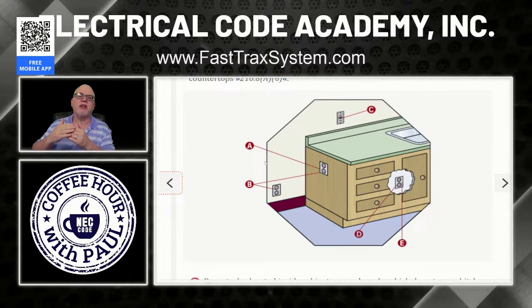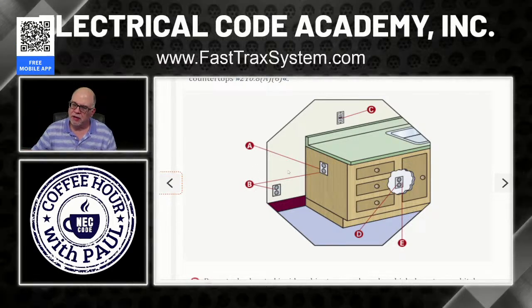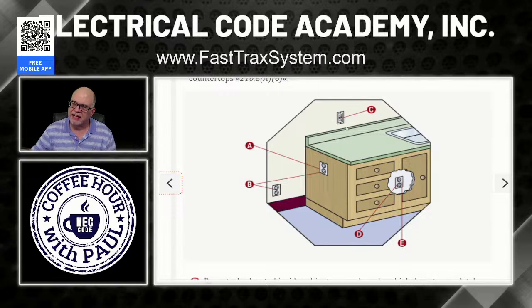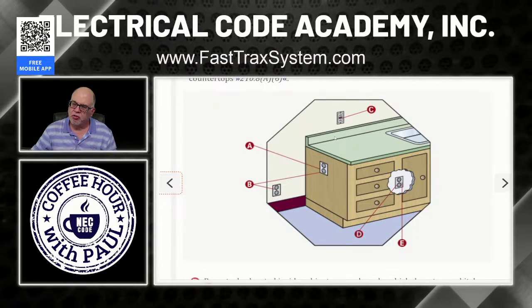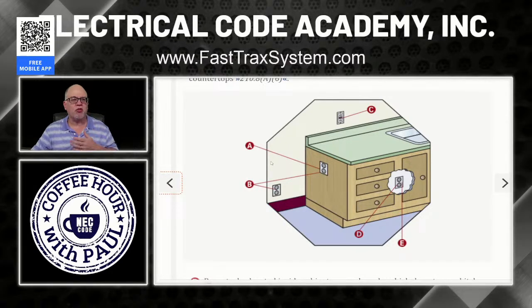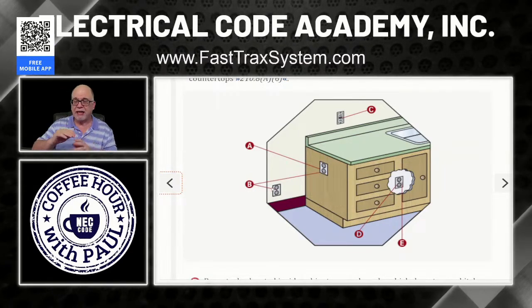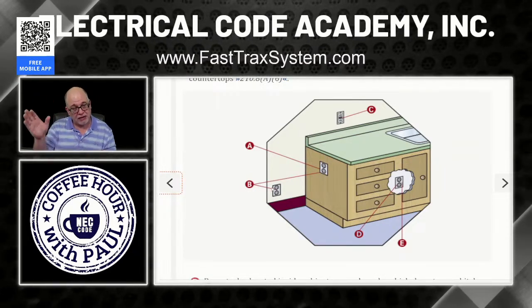So I have to have a receptacle within 6 feet. Well, this wall space over here, let's say I'm counting this right here, and I could not use this receptacle serving the counter to also serve this wall space. This is only for the counter. It's not for the wall space. So all this is saying is the ones for the countertop serve the countertop. The ones for the wall spacing serve the wall spacing. The one on the wall can't serve the countertop. The one on the countertop cannot serve the wall.